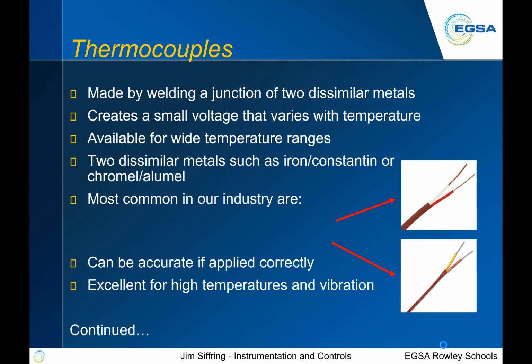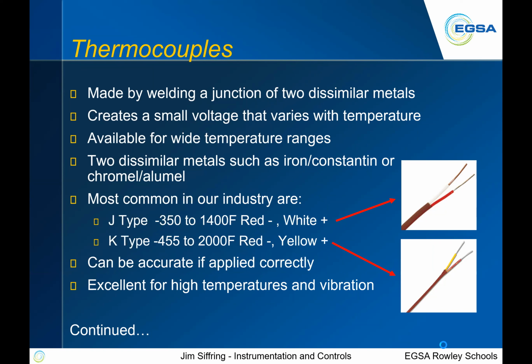So very common in the industry is a J-type thermocouple or a K-type thermocouple. Both of them, J-type is super common. With thermocouples, a J-type is an iron constantan. And so you have one wire that's made of iron. You have one wire that's made of constantan. And you join those two together. So those two wires would get welded together.